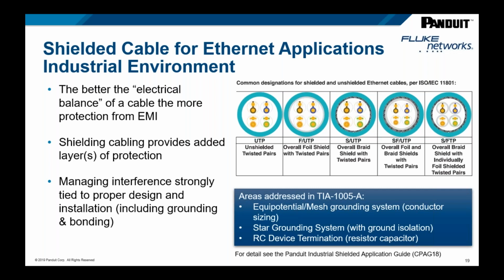What we always recommend in evaluating the cable is to first look at the electrical balance of the cable, whether it is shielded or unshielded. So including the UTP cable that you're evaluating, look at that electrical balance. And the balance is really the dimensional and electrical symmetry between each pair. As an example, the Cat6A cable standard actually requires this symmetrical design, dimensionally and electrically. As a result, using Cat6A cable, you know it has a better balance and EMI noise immunity than previous cable types. And we're seeing a lot more Cat6A cable being used on plant floors.